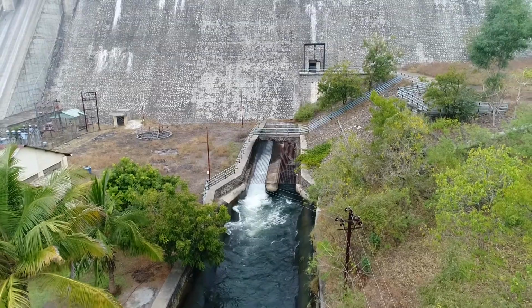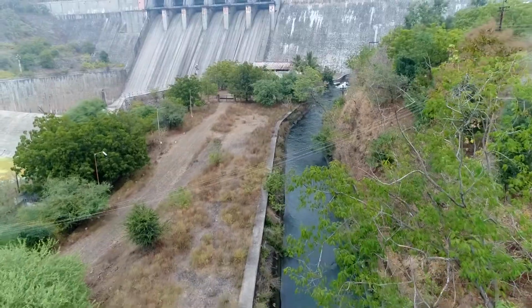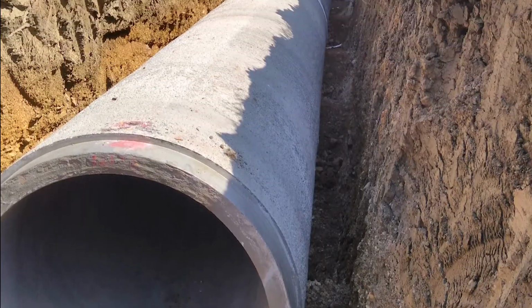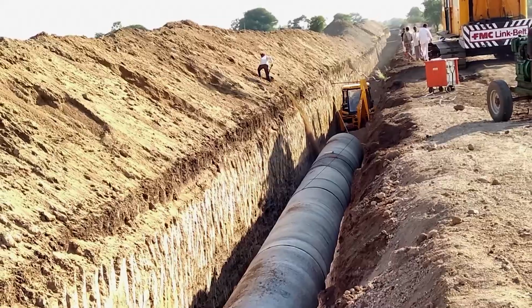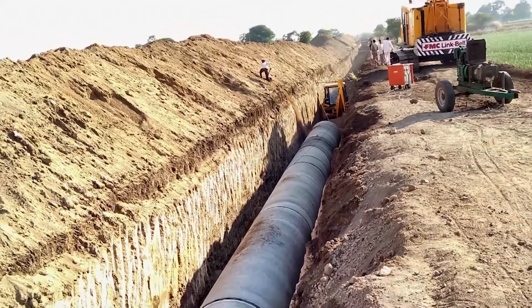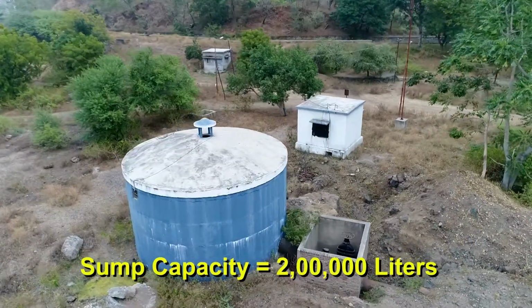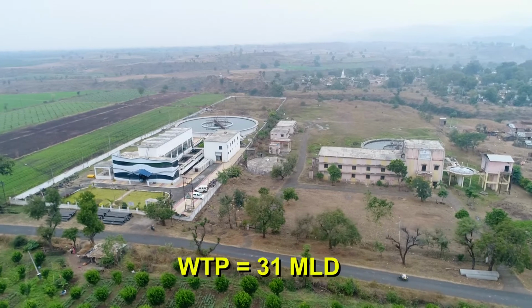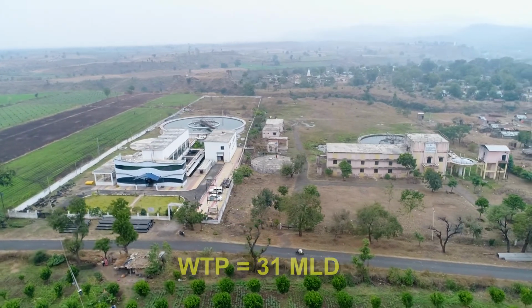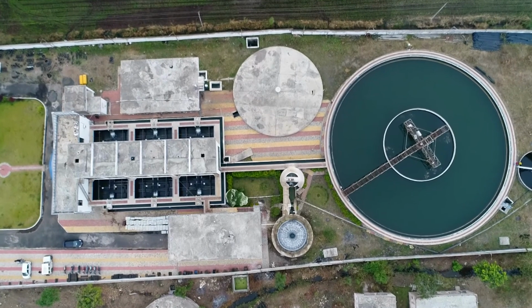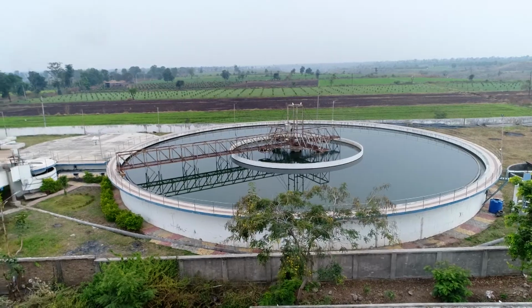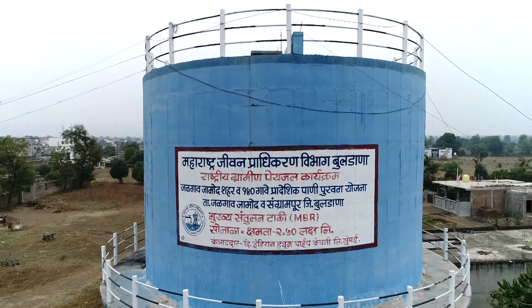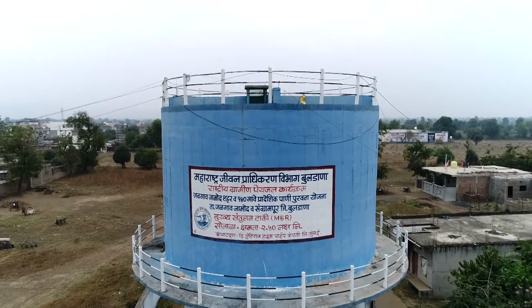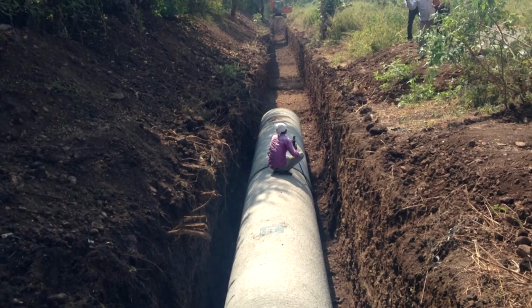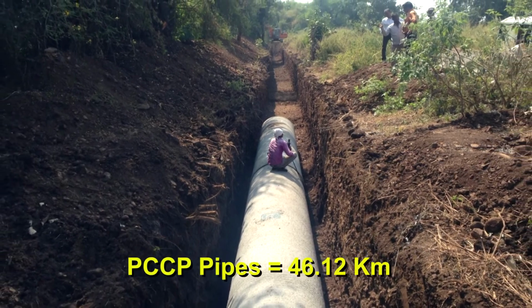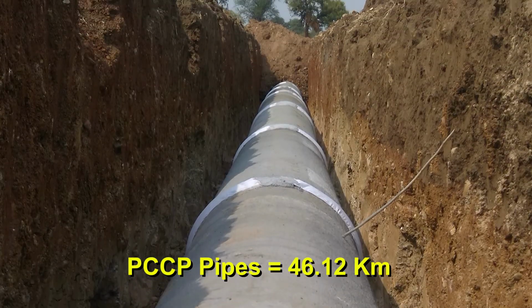Intake of raw water was taken from the canal of the Van Dam on the Purna river, where pre-stressed concrete cylinder pipes of 700 mm diameter were used for 1780 meters as a raw water gravity main from a sump of 2 lakh liters capacity to the 31 million liters per day water treatment plant or WTP. After water treatment, the network of pure water distribution consists of a principal gravity main line from the WTP to the master balancing reservoirs or MBRs using PCCP pipes of different diameters varying from 1000 mm to 600 mm for a length of 46.12 km.